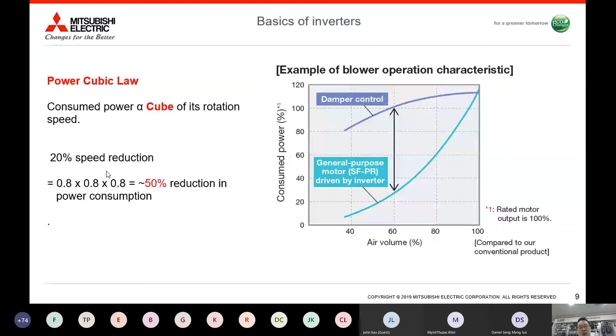If you see the diagram on the right, it shows the consumed power versus the airflow speed. The dark blue line shows the control using a damper, and the light blue line shows the use of an inverter. The area under the curve is basically the energy saving. So for a 20% speed reduction, there will be about a 50% reduction in power consumption, using the cubic law. And a 50% reduction in power consumption translates into a fair bit of energy savings in terms of dollars and cents.